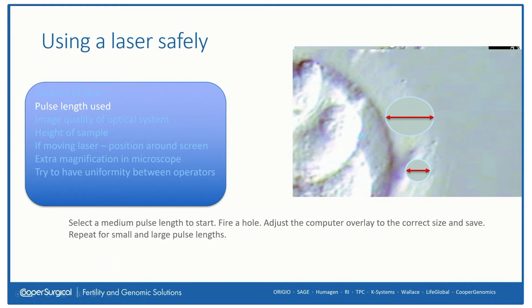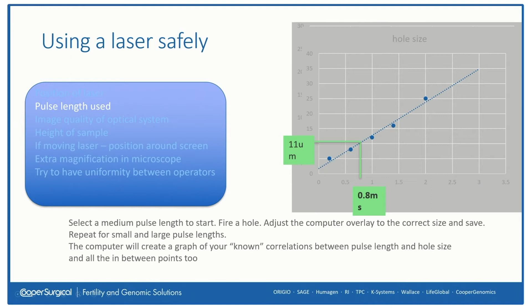Then we do the same for a small and big hole, and we can repeat this step several times, which then actually gives us a graph showing us the points that we've made which correlate between pulse length and actual hole size. Then the PC, the computer, uses these points to cover any step in between. So for instance, if I chose a pulse length of 0.8 milliseconds, the computer would expect to see a hole size of approximately 11 microns in the zona, and that's how it calculates and shows us these graphic overlays.